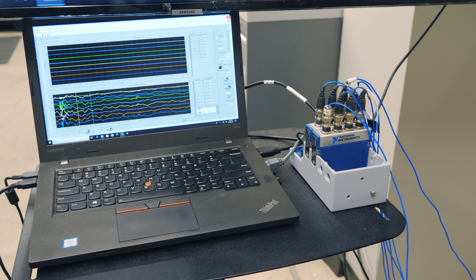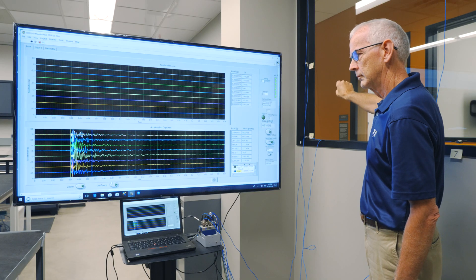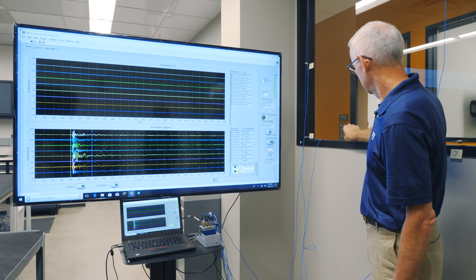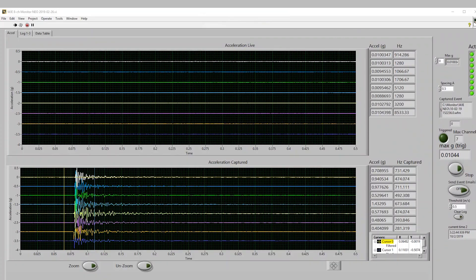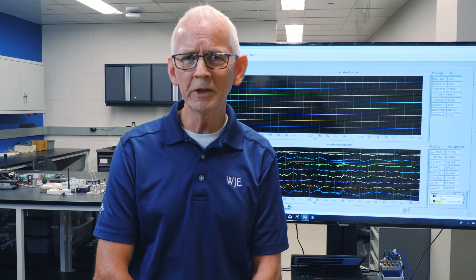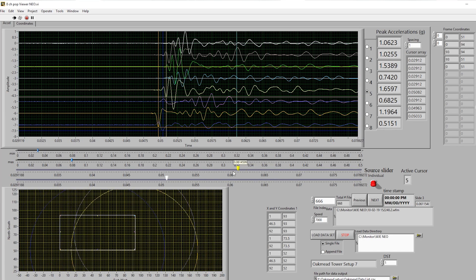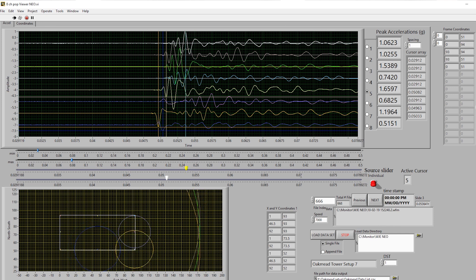The computer is running a program written in LabVIEW that is continually scanning all eight sensor channels at a rate of 51 kilohertz in order to capture high frequency acceleration waveform data if a vibration event occurs. The program is continually waiting for these events to occur, and can run 24/7 and save those triggered events as waveform files that we can remotely access.